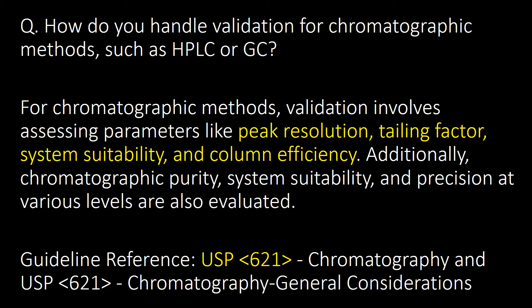How do you handle validation of chromatographic methods such as HPLC or GC? For chromatographic methods, validation involves assessing parameters like peak resolution, tailing factor, system suitability, and column efficiency. Additionally, chromatographic purity, system suitability, and precision at various levels are also evaluated. Guideline reference: USP Chapter 621.